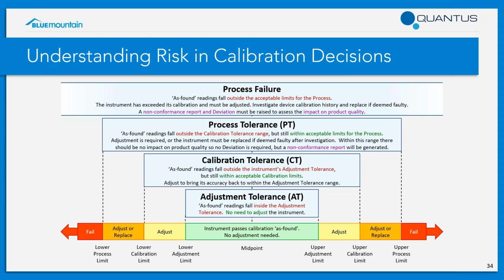I'm going to work from the bottom of the slide upwards. Each instrument, in terms of its calibration, will have a midpoint, a perfect point at which it would be absolutely in the center of its allowable tolerance for that process. The pale green section in the bar at the bottom reflects what we call the adjustment tolerance. It goes from a low limit to a high limit, or adjustment limit. When the calibration technician is checking the calibration of that instrument, if the as found readings fall inside of the adjustment tolerance, that's great. Everything's good and there's no need to adjust the instrument at all.